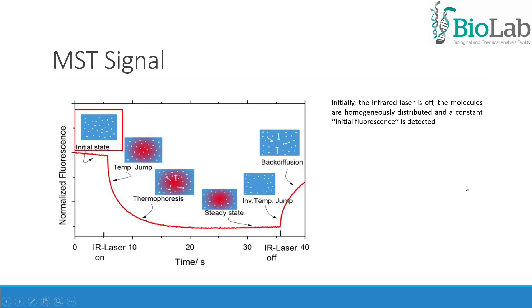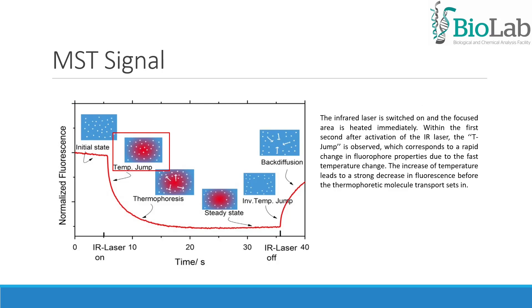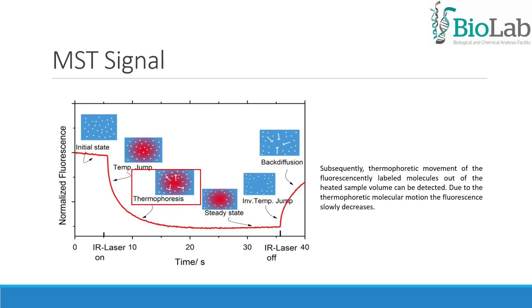In an MST experiment, initially the infrared laser is off; the molecules are homogeneously distributed and a constant initial fluorescence is detected. Then the infrared laser is switched on and the focused area is heated immediately. Within the first second after activation, the T-jump is observed, which corresponds to a rapid change in fluorophore properties due to the fast temperature change. The increase of temperature leads to a strong decrease in fluorescence before the thermophoretic molecule transport sets in. Subsequently, thermophoretic movement of the fluorescently labeled molecules out of the heated sample volume can be detected, and the fluorescence slowly decreases.